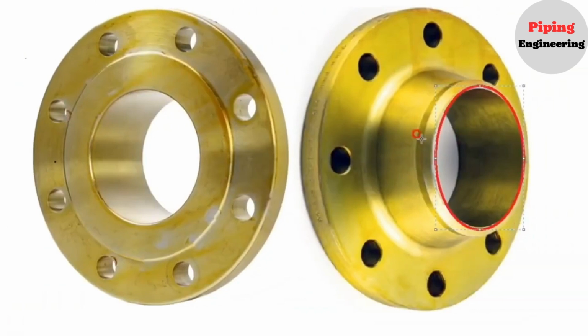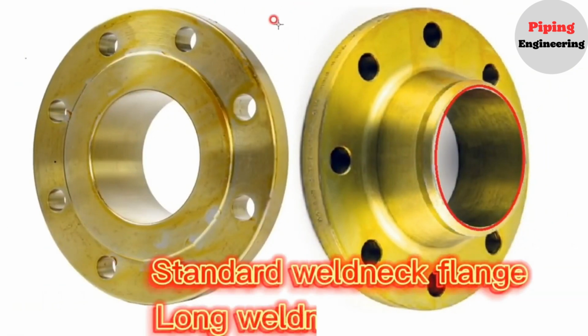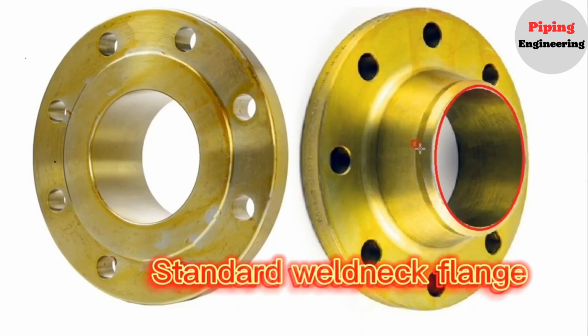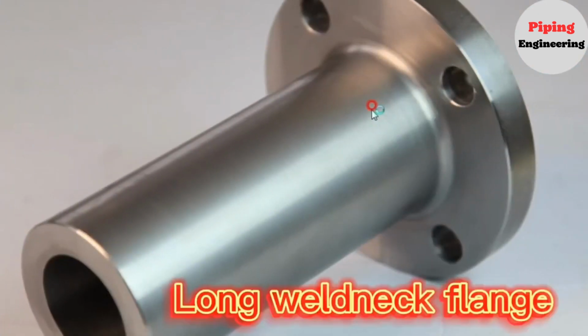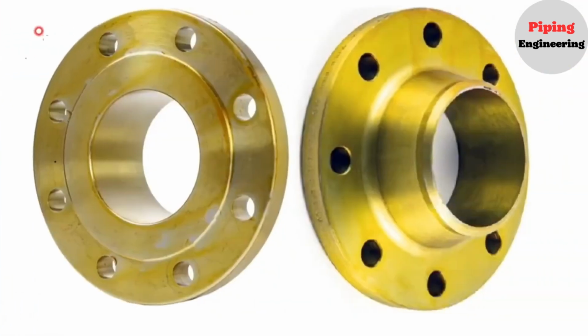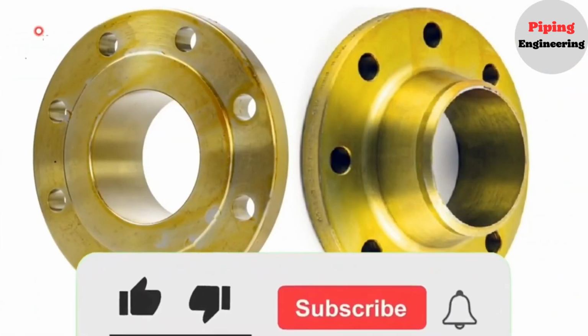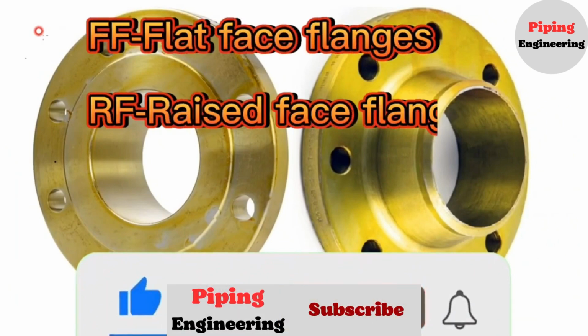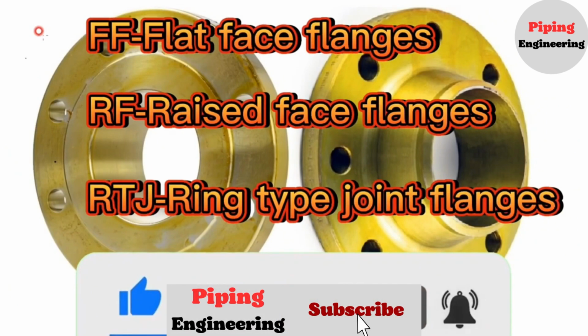There are two types of weld neck flanges, which are standard and long. Standard weld neck flanges are used in butt weld fittings. Long weld neck flanges are used with vessel nozzles and equipment. The flanges are created to match the pipe's inside diameter or fitting. Weld neck flange is available in all sizes and it can be FF, RF, or RTJ type.